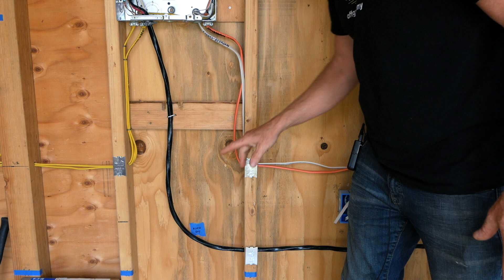Now, another thing you might want to think about here, if you're planning on adding any type of an off-grid setup in the future, is just bringing your service line in a convenient location so you can add either a grid-tied inverter or a transfer switch without having to do major surgery inside your walls. And even though I'm not showing it right here, if you leave a little bit more slack than this in this loop, you'll be able to do a splice somewhere in this area into that equipment without having to pull your service all the way out of your box. So that's something to think about as well.